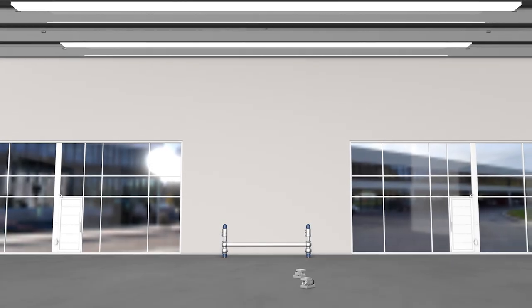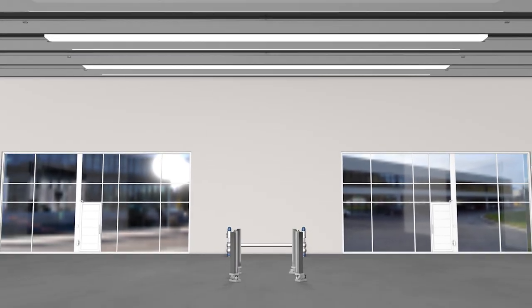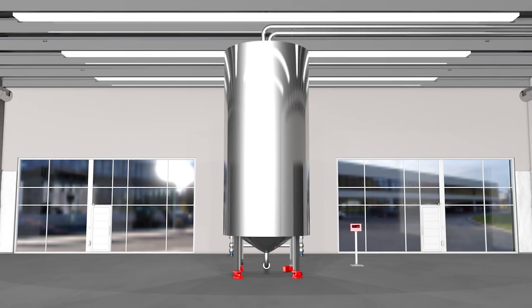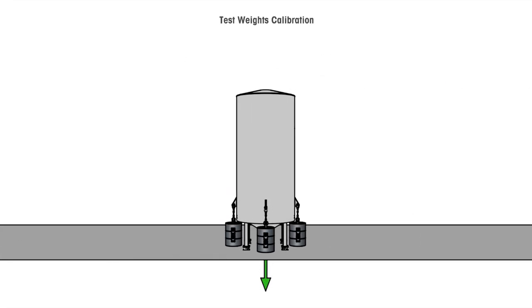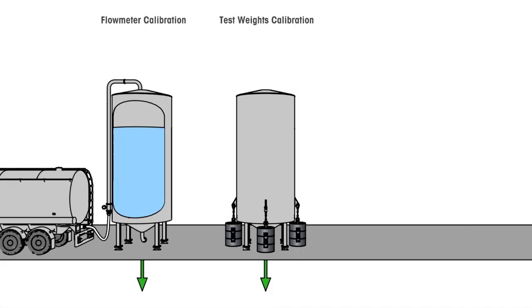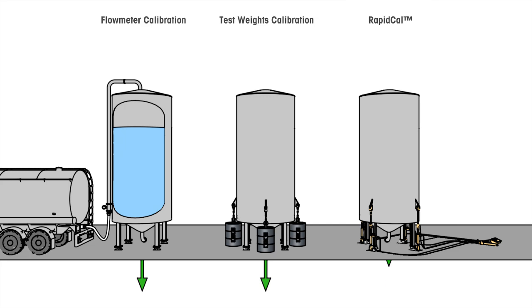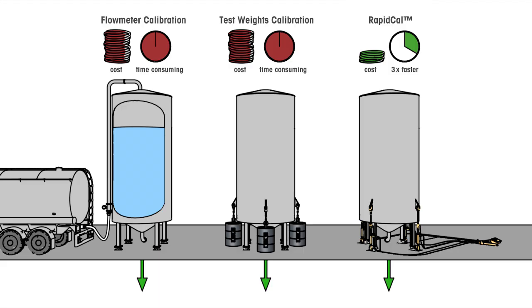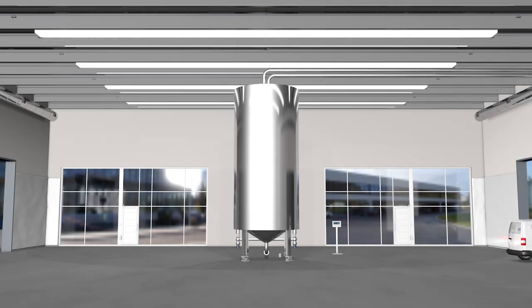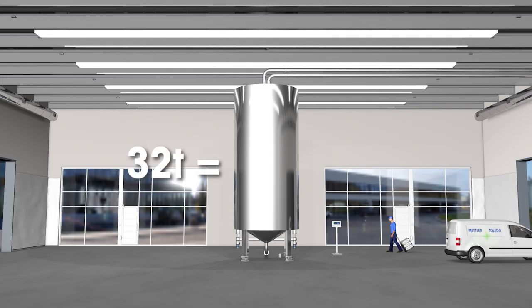METTLER Toledo provides components such as weigh modules, junction boxes, and terminals to turn your process or storage tank into a scale. Were you ever wondering how to calibrate your tank scale and achieve precise weighing results even for high capacities? We have the answer to your question. Instead of using dead weights or filling expensive material in the tank, the downward force is applied by hydraulic equipment. With METTLER Toledo RapidCal Tank Scale Calibration, your tanks and silos can be calibrated up to 32 ton.